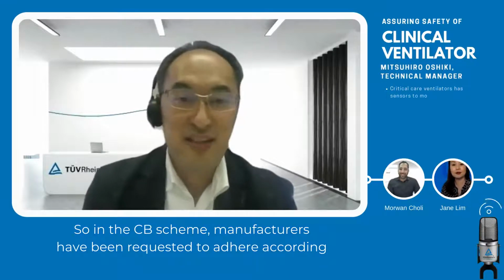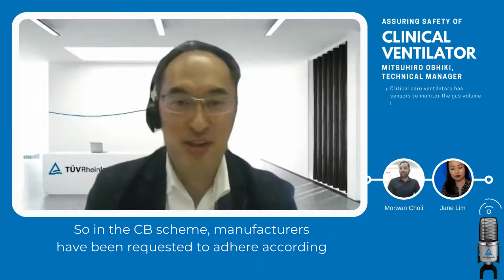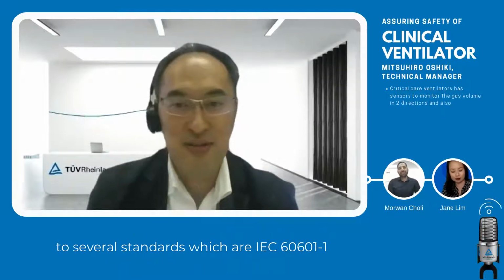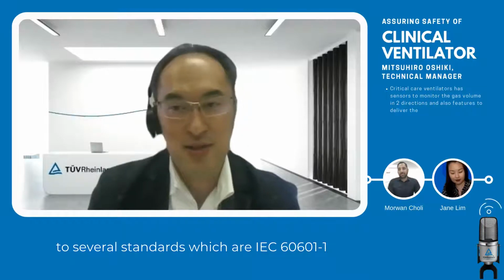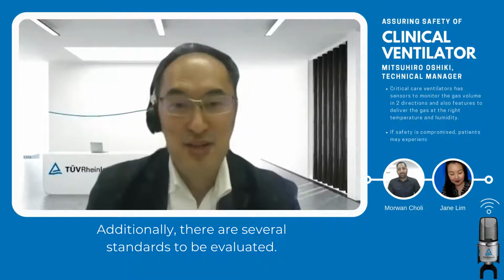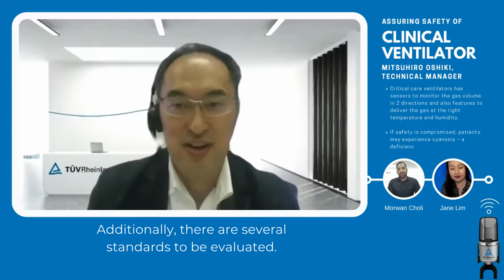So in the CB scheme, manufacturers have been requested to evaluate the ventilator according to several standards, which are IEC 60601-1 and ISO 80601-2-12. This is a successor of IEC 60601-2-12. Additionally, there are several standards to be evaluated with these standards, such as IEC 60601-1-2 for EMC evaluation, IEC 60601-1-6 for usability, and IEC 60601-1-8 for alarm systems.